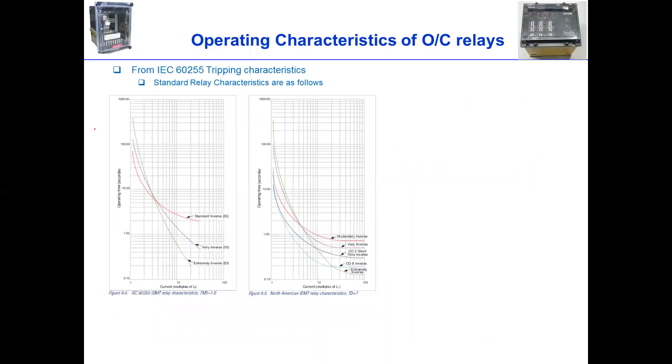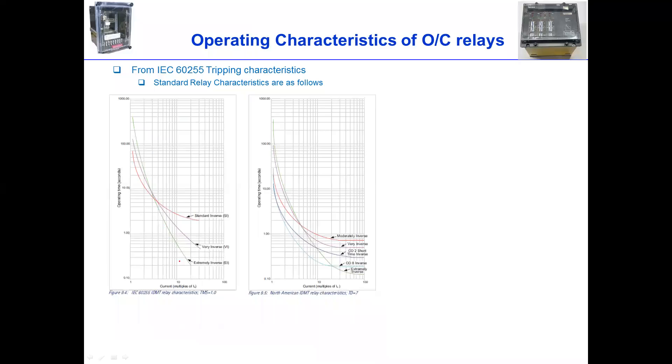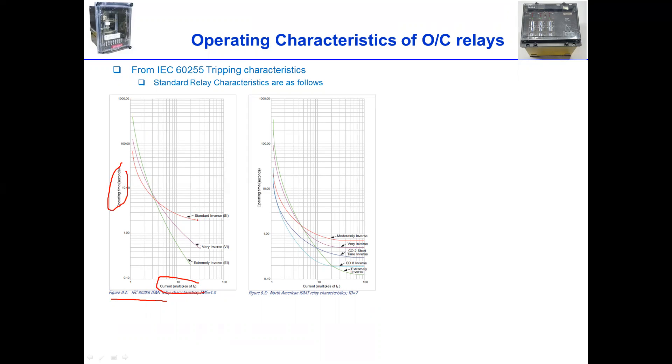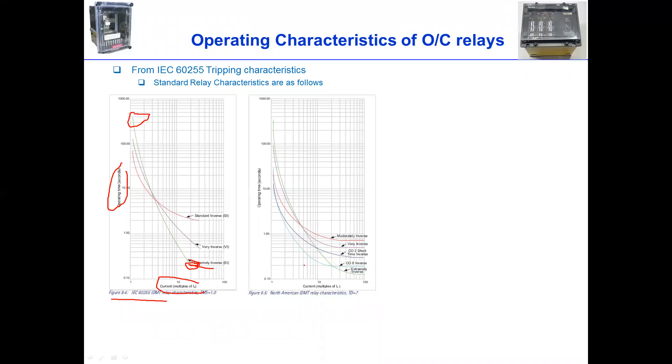From IEC 60255 tripping characteristics, we have this kind of characteristics provided. As you can see, we have standard inverse and extremely inverse. So this is the current multiple of secondary current against the operating time of relay. As you can see, this is the standard curve, which is a bit slower when the fault current is at high. And of course, the extreme inverse is a bit faster trip time when the fault is high, but slower at low fault.